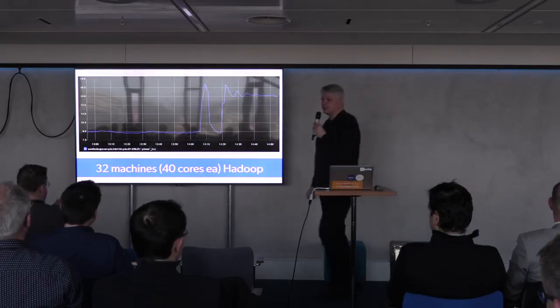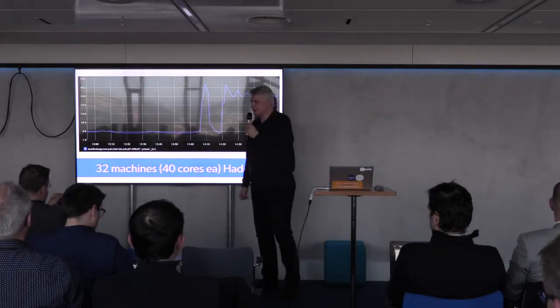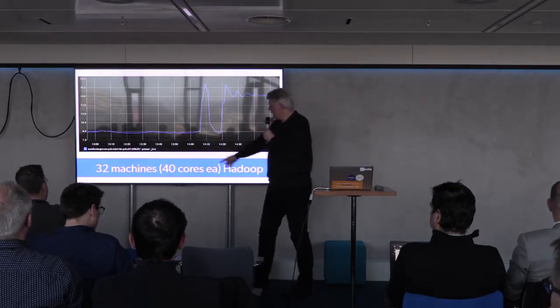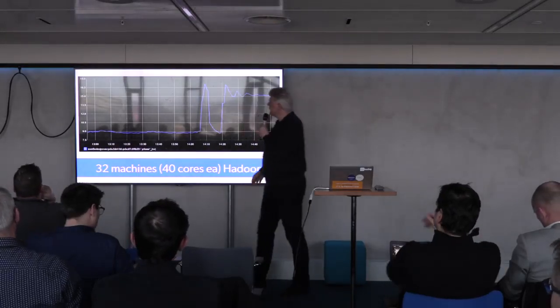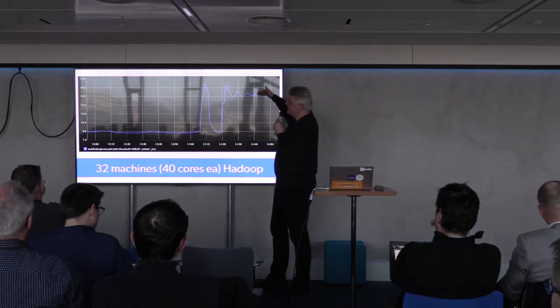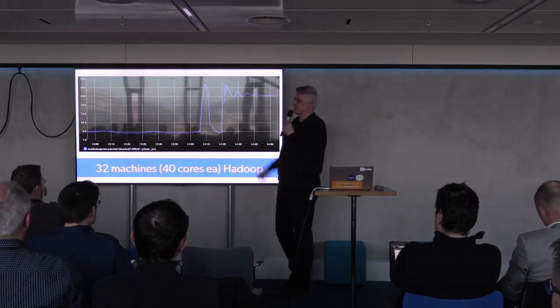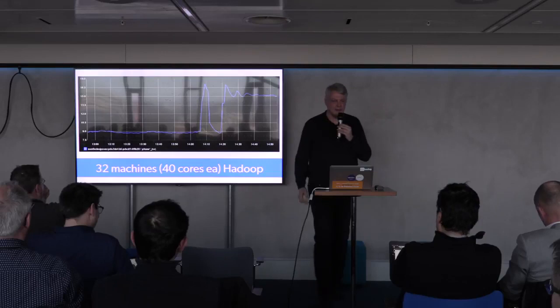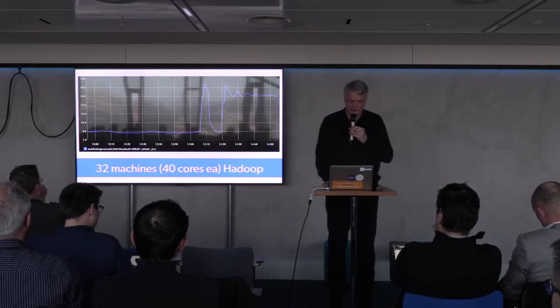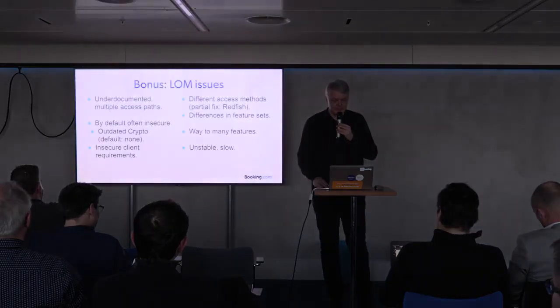I got 32 because I had 8 LOM failures during provisioning. These are Hadoop machines, 40 core boxes, and I get this 7 kilowatt rack running at 15 kilowatts here, so that's a huge overcommitment into a hotspot, which required additional cooling in this case.